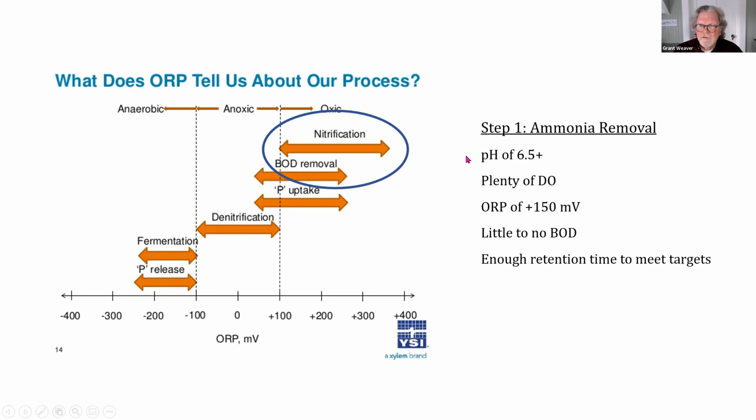pH for folks with soft waters is critical. You can get partway through ammonia removal, but once the pH drops below the number I've seen is 6.45, then you're going to have a lot of nitrites.